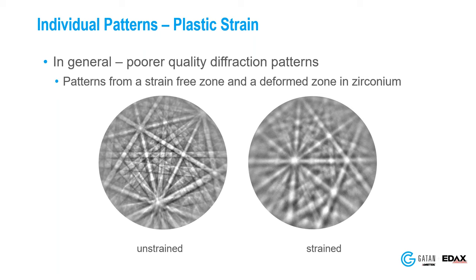Question: How do you differentiate between elastic and plastic mapping in EBSD? Plastic deformation we can see through subtle changes in orientation across the map. With elastic strain, the patterns themselves slightly distort, so to really look at elastic strain you need to use HR-EBSD, which is based on cross-correlation of patterns. If you're looking at plastic strain only, you can measure that through subtle orientation changes detectable with traditional EBSD work.